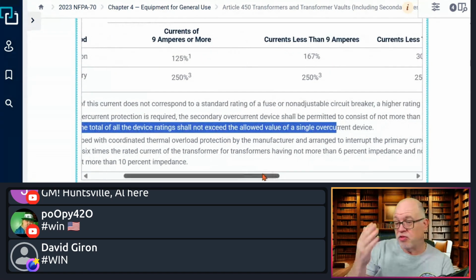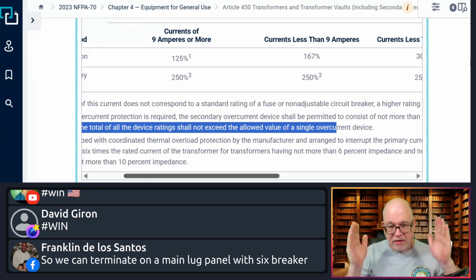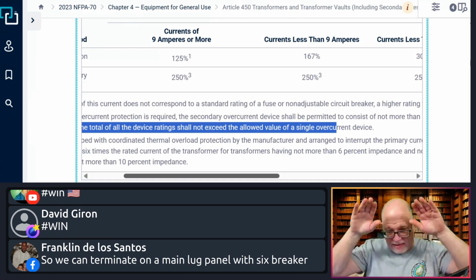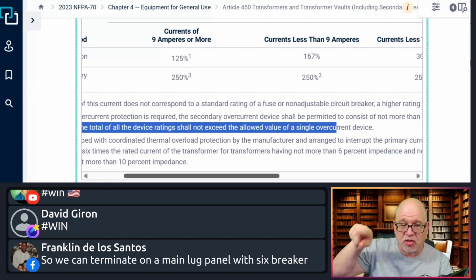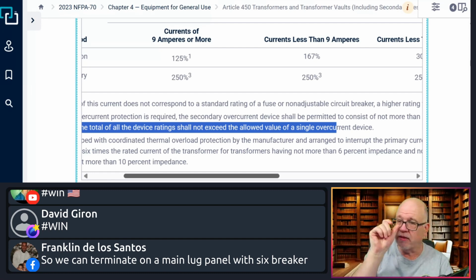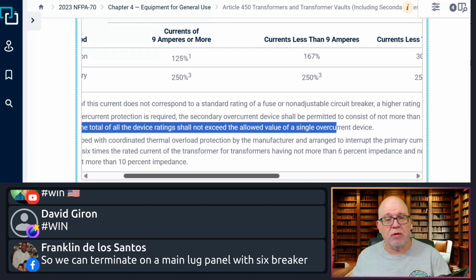So again, if this was a 200 amp panel, 200 amp secondary, 200 amp panel board protection, and I wanted to have the 6 disconnects, right? I wanted to have that allowance in there. So basically hitting the main lug and then having 6 of the disconnects there. Cumulatively, adding them up just by taking the number that's on the escutcheon, whatever's posted on it, like a 50, a 50, a 50, collectively they cannot exceed, adding them up, what it would be if you just chose a single breaker to terminate into, okay? So it is limiting you, but it does allow you to have the 6 in a panel board, in a single enclosure.